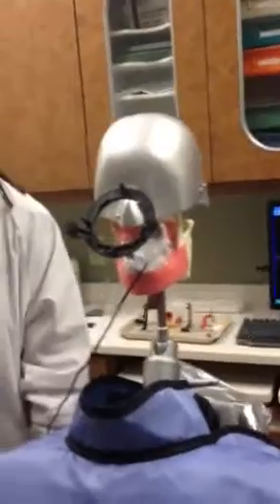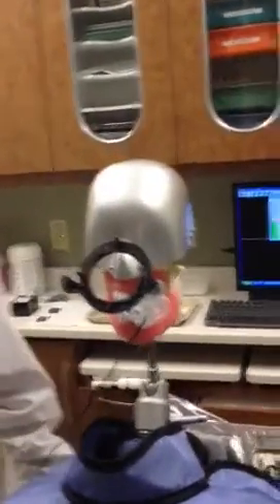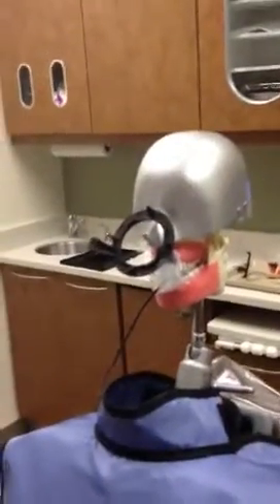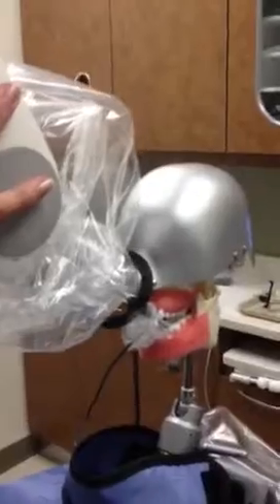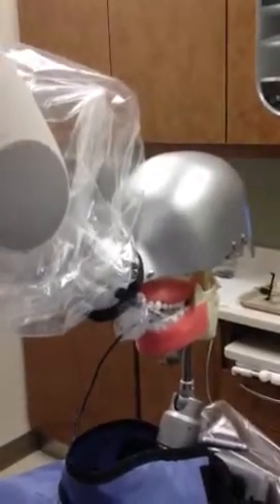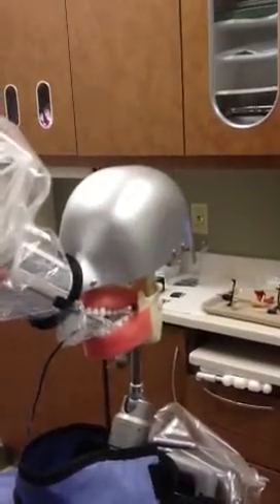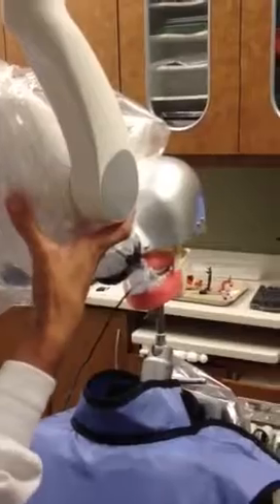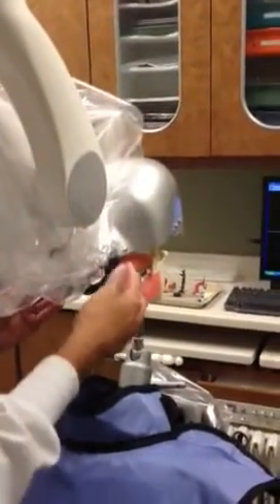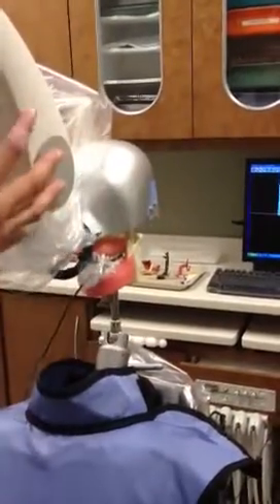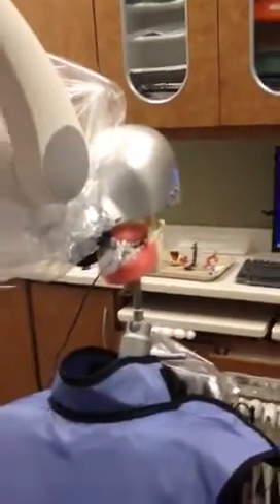I'm just going to put the chair down a little bit so that it's at the right height for me. And it's important that you're lining up the PID, that's position indicating device, so it's parallel with the metal part of the holder. So you want to make sure the power's on. Flush with the circle, and then we'll have everybody just head outside of the room.